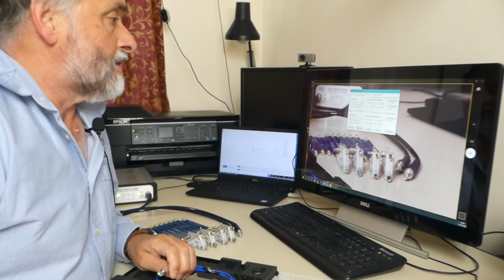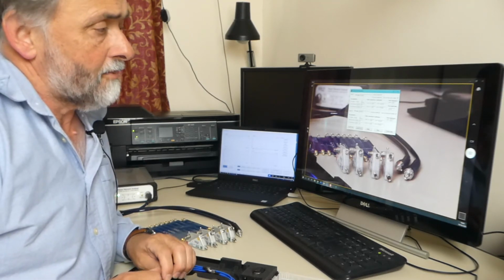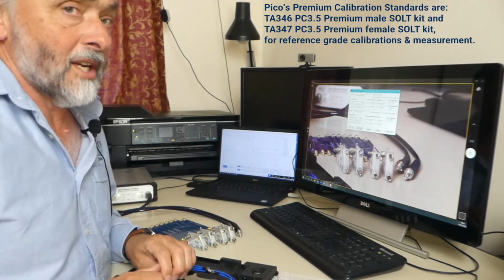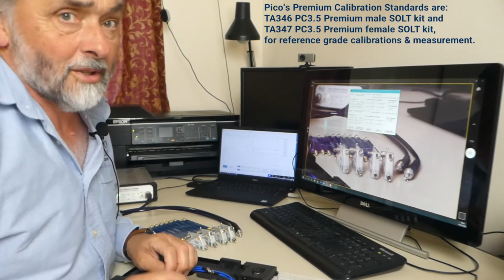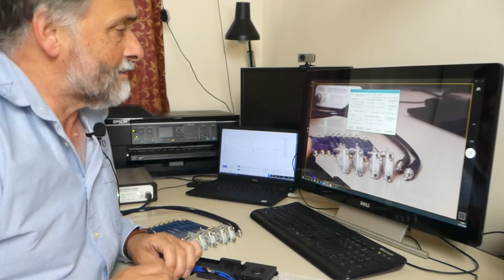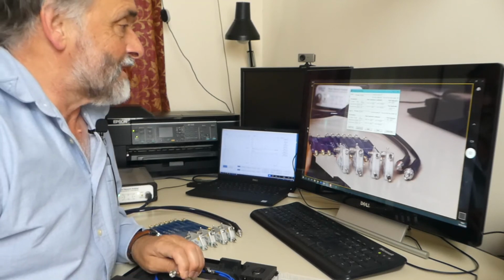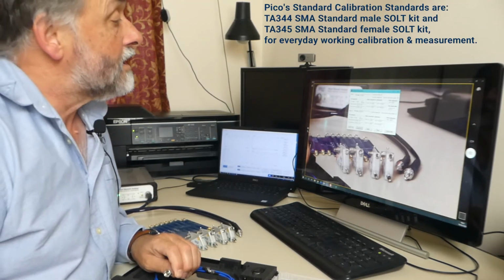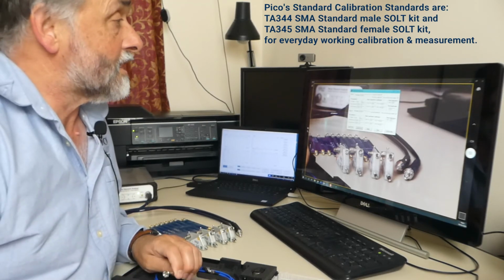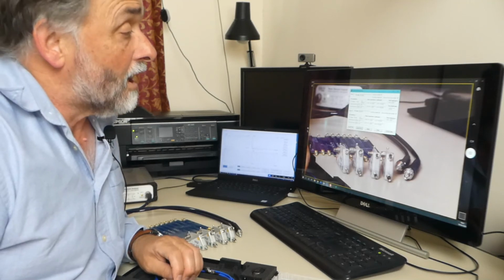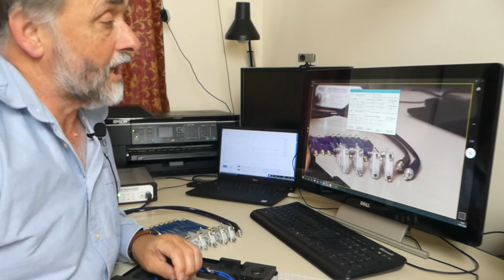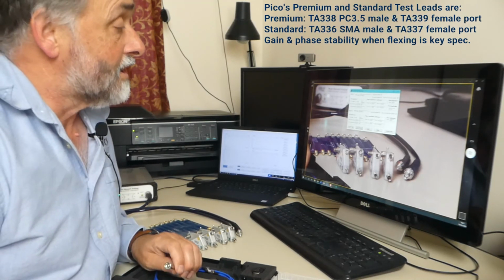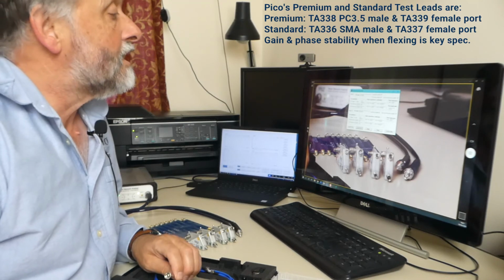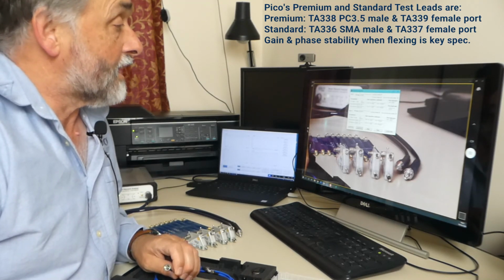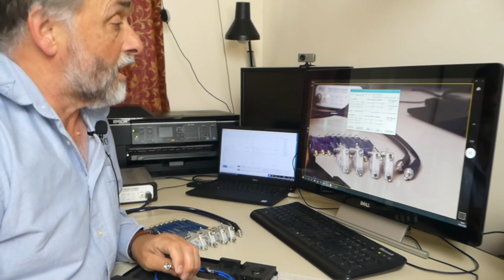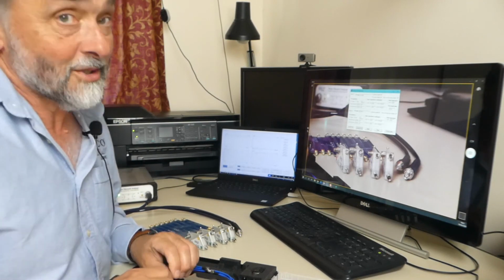So premium standards, we could use them with these SMA connectors. Some would say that if there's an SMA in the measurement, because that alone brings some uncertainty into the measurement, you might as well use SMA standards. We can argue that. And it is largely our intent that these working test leads, whilst extremely good, are slightly less stable for their gain and phase than our precision test leads. So we would recommend, when you're using these SMA working test leads, that you use SMA calibration standards, and we would use premium standards when we're making a premium measurement using premium test leads.